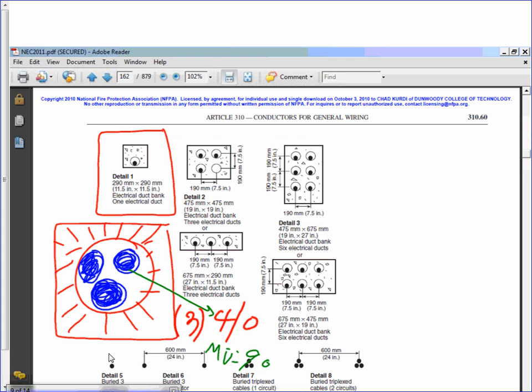They're called details. This is based on detail 1. What they do is they have 11.5 by 11.5 inch concrete for these medium voltage, and they have a duct, a conduit encased in concrete, to protect the medium voltage cable, and they put it underground. When you look at it, it looks something like this: a conduit encased in concrete with 3 conductors inside it. Each one of them is 4 aught. And the installation is medium voltage, 90. You probably have never heard of that or seen that.